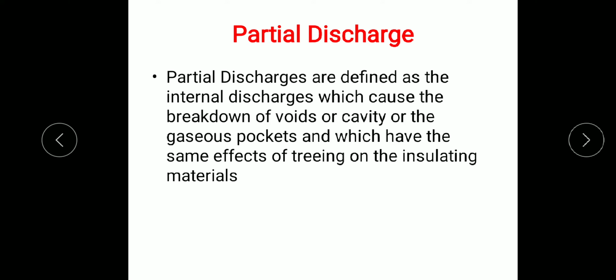Partial discharge is defined as the internal discharge which causes the breakdown of voids or cavities. Voids or cavities mean holes or gaseous pockets, and they have the same effects as treeing on insulating materials. For example, when you apply voltage on a solid material, due to capacitance action, charges are induced in the voids. Voltage due to the electric field is developed in the voids. Whenever the voltage of the void reaches the breakdown strength of the void material, breakdown will occur. That is what partial discharge is.